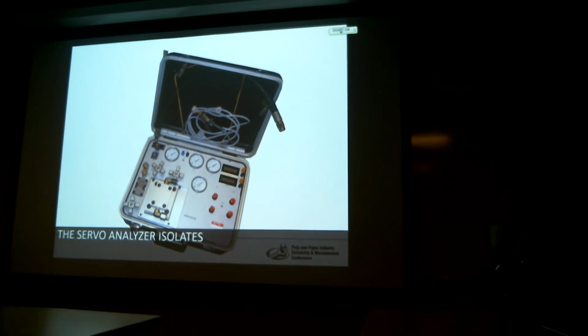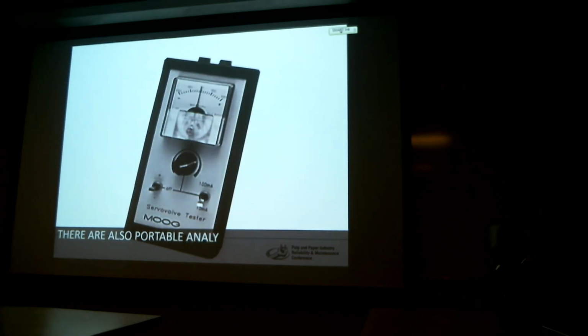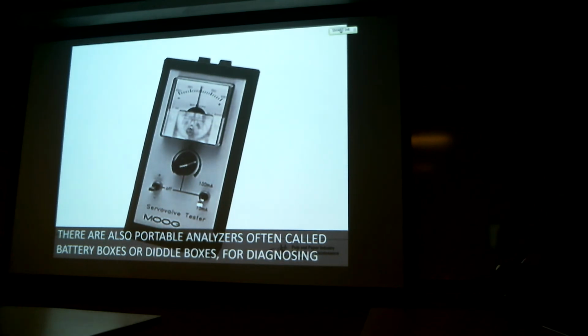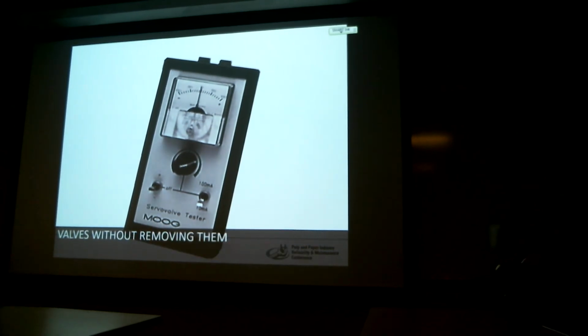The servo analyzer isolates the servo both electrically and hydraulically to determine this condition. There are also portable analyzers, often called battery boxes or diddle boxes, for diagnosing valves without removing them from the system.